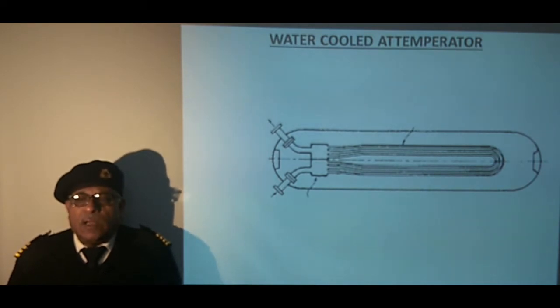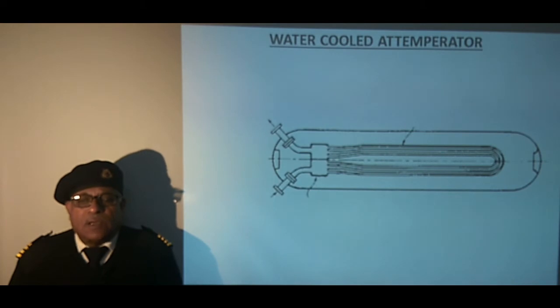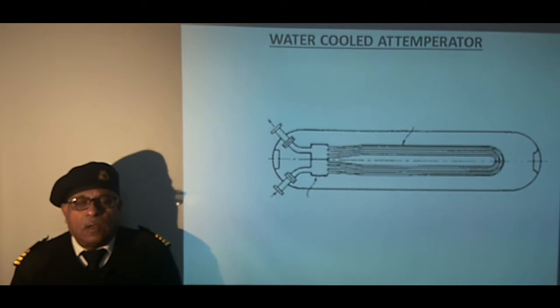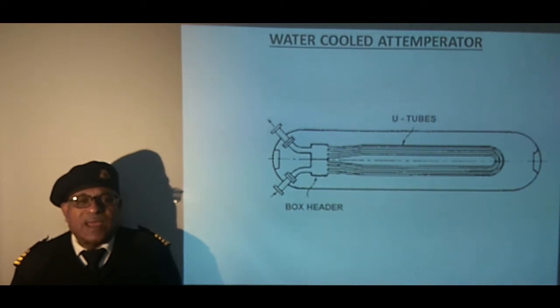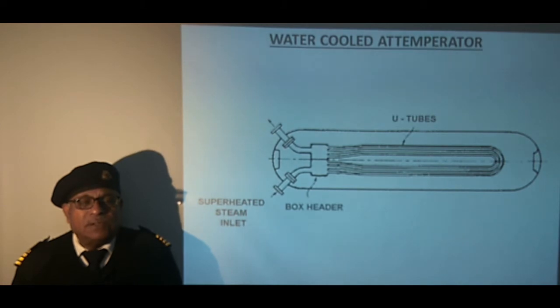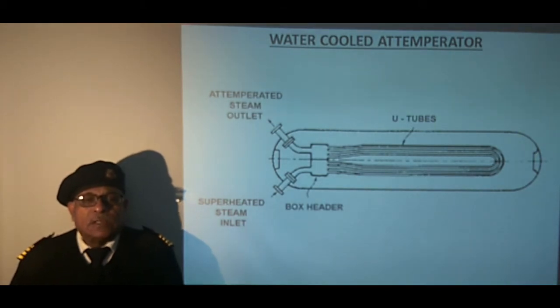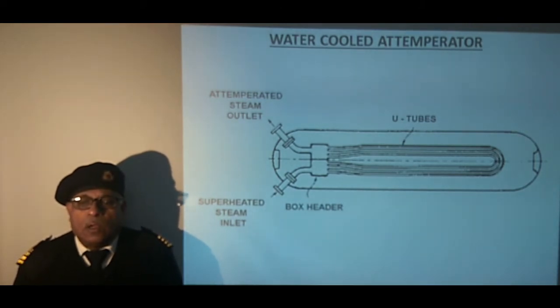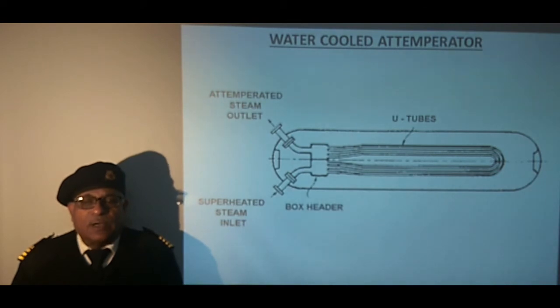This sketch shows an integral surface type water-cooled attemperator which is located in the steam drum. Let us see the components of the attemperator and the flow of steam through it. We can see the box header to which U-tubes are attached. Superheated steam enters at the bottom connection of the header and leaves from the upper end of the box header to the secondary superheater. U-tubes attached to the header are submerged in water, which gives up their heat to the surrounding water. Supply of steam to the attemperator is through a three-way valve, which is used to automatically maintain the steam temperature through a controller.